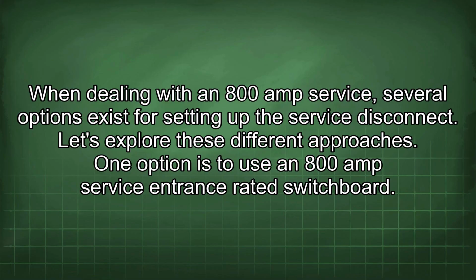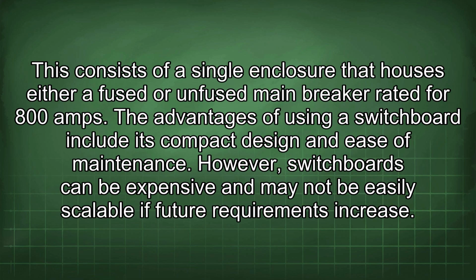When dealing with an 800 amp service, several options exist for setting up the service disconnect. Let's explore these different approaches. One option is to use an 800 amp service entrance rated switchboard. This consists of a single enclosure that houses either a fused or unfused main breaker rated for 800 amps.